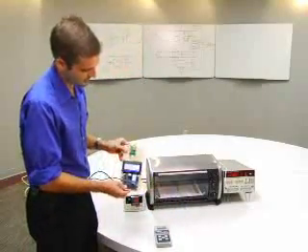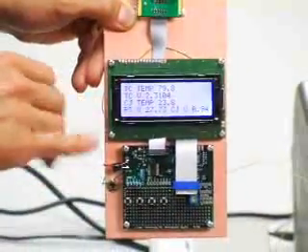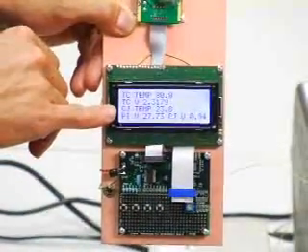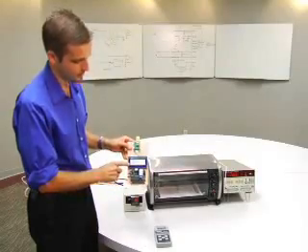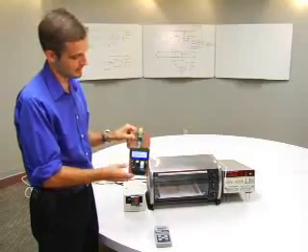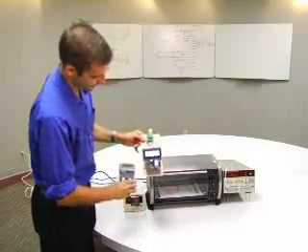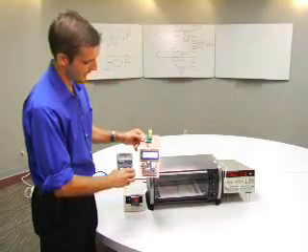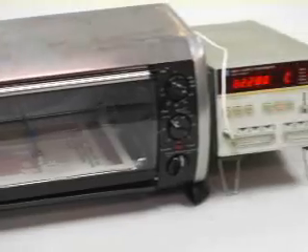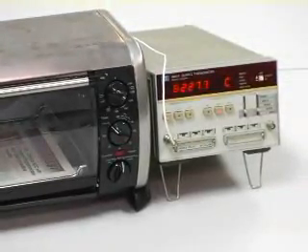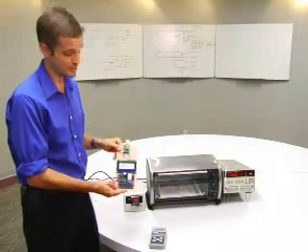So let's look at a few of the numbers here. The calculated thermocouple temperature is about 79.9 or 80.1 degrees. We've got a couple tenths of a degree of flicker, which is about what you would expect given the 600 nanovolts noise of the A to D converter itself, which compares quite well to the 79.8 degrees read on the commercial meter. And we're still a couple degrees off from the quartz thermometer. It's different sensors, and this is not exactly a first-class calibration setup.